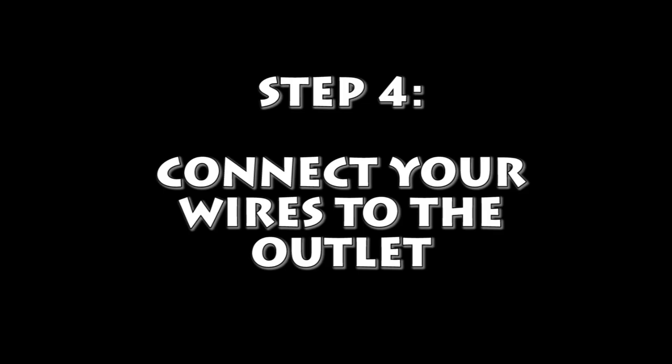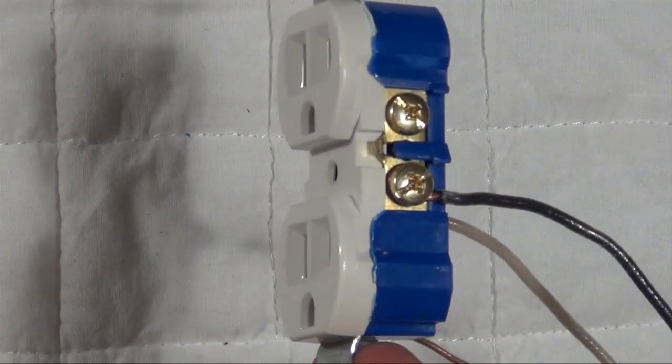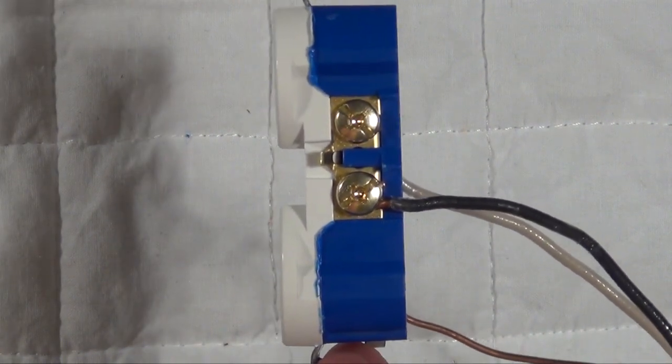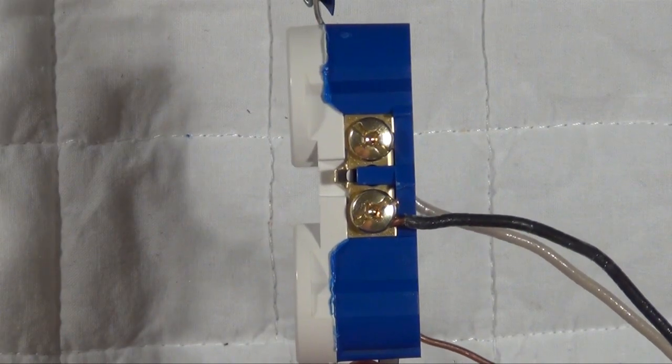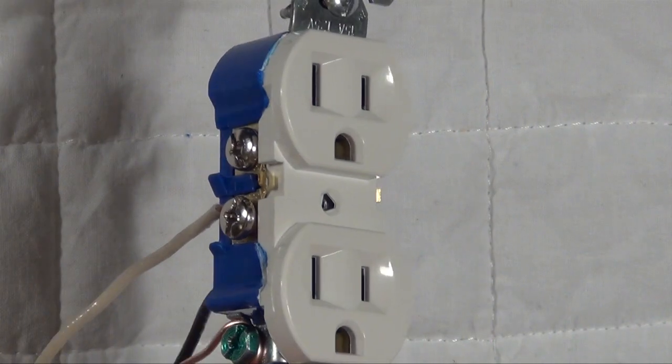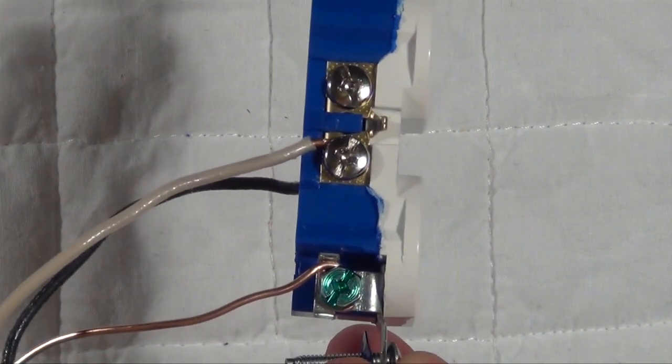With your loops created, you can match up your wires to the appropriate screw. Under most, but not all, conditions, your black wire will loop around the brass-colored screw, your white wire will loop around your silver-colored screw, and your bare ground wire will loop around the green screw.